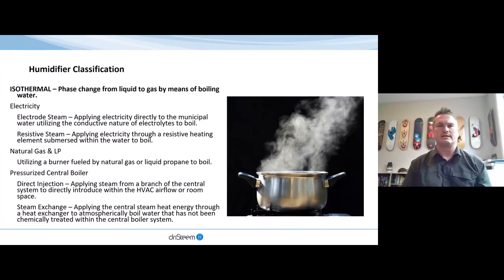So after discussing the preservation of artifacts, the role that relative humidity can have with that, and looking at relative humidity as part of the strategy for reopening and how that could benefit, let's look at a couple of the different types of humidifiers that are available currently. There's isothermal, which is a more traditional means of humidifying. Isothermal means to make a phase change from a liquid to a gas by means of boiling water. So it's nothing evolutionary or new, but we have different energy sources to make this happen. One being electricity. There's electrode steam, which is applying electricity directly in the water and using the electrolytes of that water to boil. There's resistive element type steam, which is applying electricity through a resistive heating element submersed within the water to make the water boil.